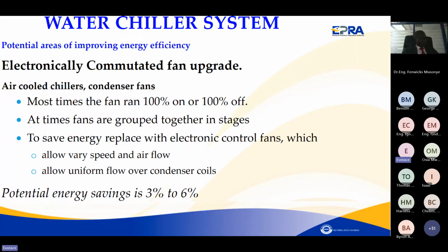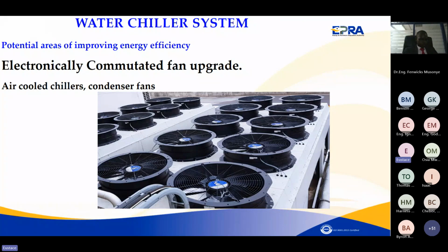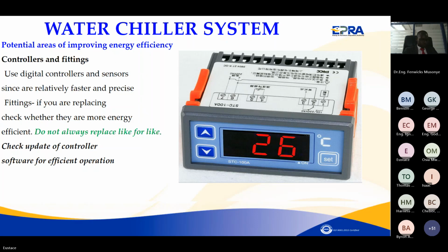Most of the time the fans run at 100%. So you need to check. You can retrofit using electronically commutated fans, which are more efficient. They have the potential of 3 to 6%. Upgrade the controllers: you can get controllers with better response, such that if you detect environmental conditions have changed, you respond as quickly as possible.